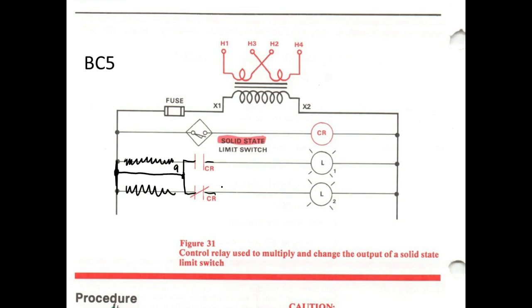So I could take one solid state sensor that only gives me one contact, and then I could run it into a control relay that's got multiple contacts. So these are not double throw, these are all single poles. But we do have some normally closed single poles and normally open single poles.